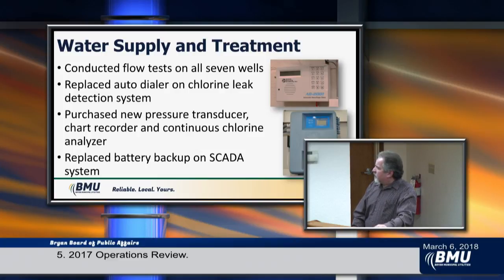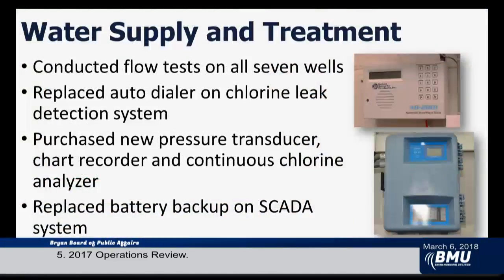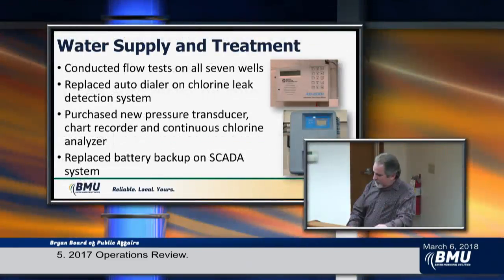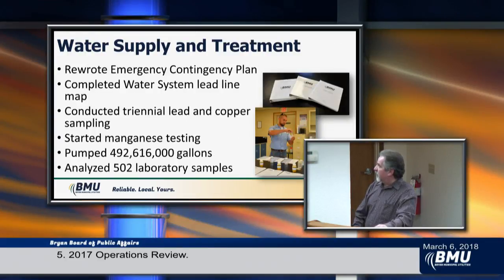We replaced the old pressure transducer and chart recorder, and the continuous chlorine analyzer, which is on the bottom right, just lets us know the concentration of the chlorine in the water as it leaves the plant at a glance. We still do our daily tests as required, but this monitor lets us know at a glance if there's any change going on. It's been a handy unit to have. And we did some battery backup replacement there on the SCADA system.